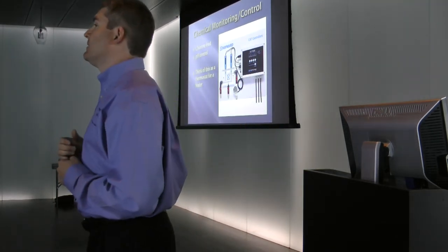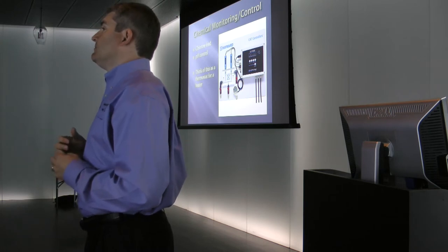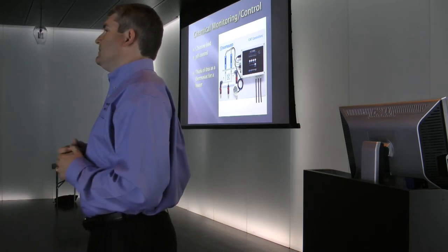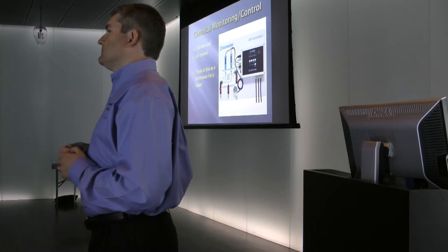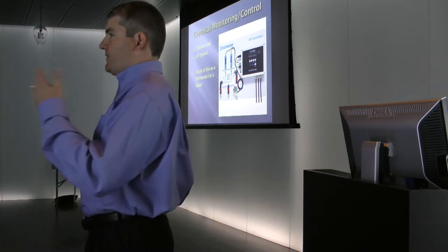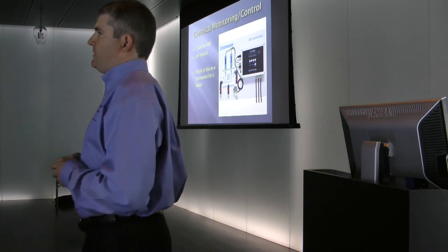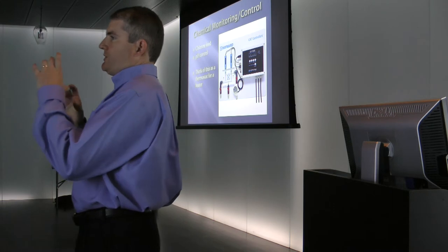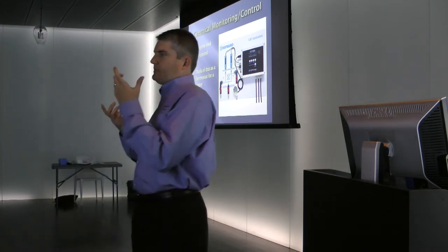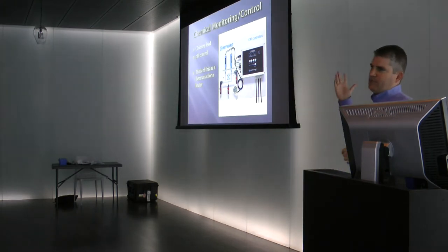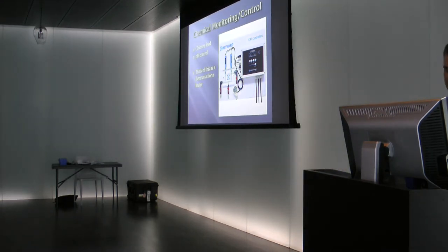Is that 2 years with daily operation, or is that a 24-month period, whereas you run it 4 months a year over 3 or 4 years, taking care of it in the off season? Yeah, you could make it last longer if you're only running it for 4 months a year. You would want to take it out and store it submerged in the KCl, which is what's really inside of it. And they're not terribly expensive. They're $100 or something for a probe.